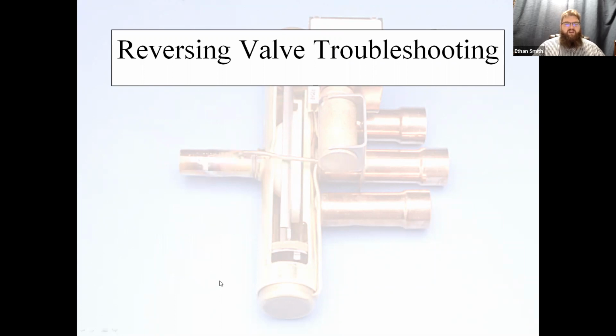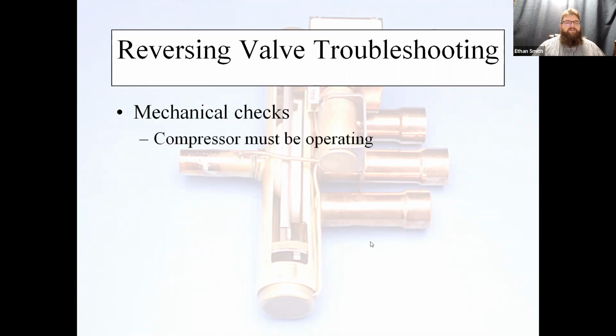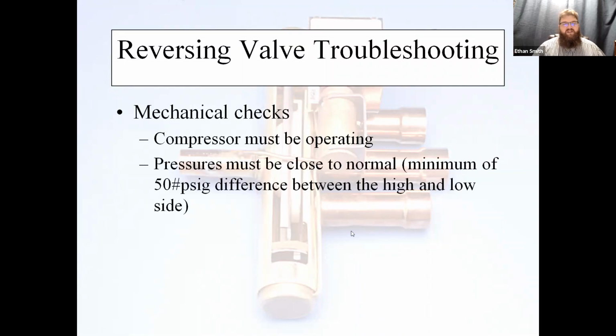Other things on a reversing valve is a mechanical failure. So we talked a little bit, we mentioned that this slide mechanism can get stuck. You do have to have the compressor running in order to do the following tests. Pressure should be close to normal. You've got to have a minimum of 50 psi difference between the high and low side to make a valve move back and forth. If you have less than 50 psi difference, you may have a refrigerant leak that's causing your reversing valve not to move over. So you may need to address that before you do this.